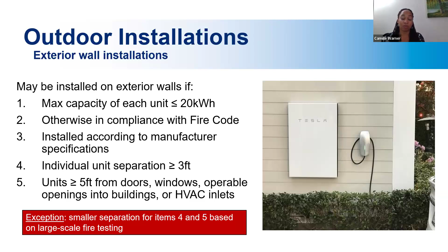Per the fire code, these units can be installed outside if they meet a number of requirements identified on the slide. These are your residential systems: less than 20 kilowatt-hours, installed according to the manufacturer's specifications, with unit separation, and more than 5 feet away from doors, windows, etc. There's an exception again for large-scale fire testing. If the fire testing says it can be placed a little bit closer, and the test can prove that, then the developer may elect to choose that option. And this should look familiar to you. It's the same as the residential code that we went over earlier.